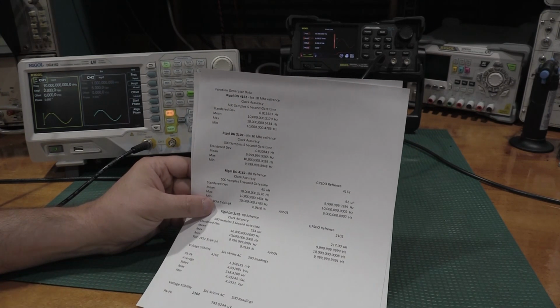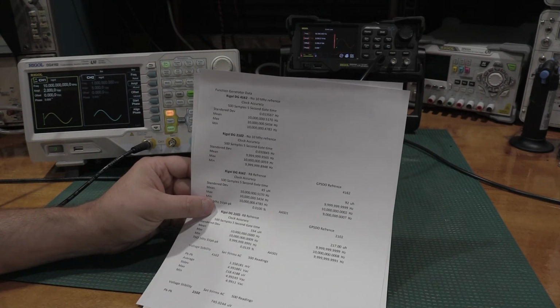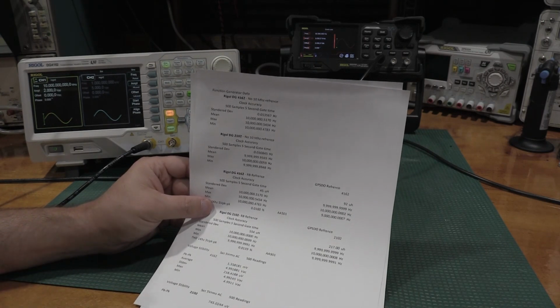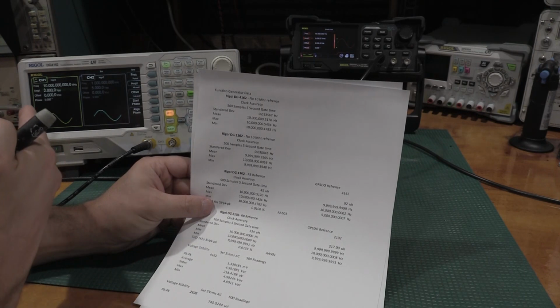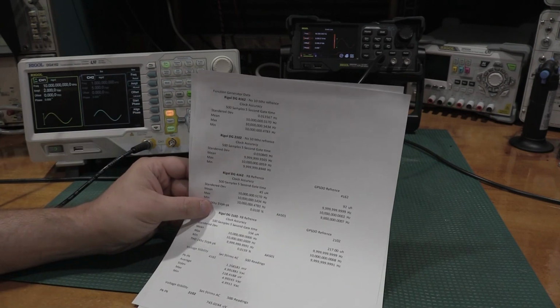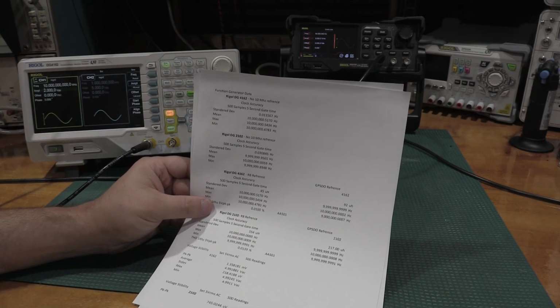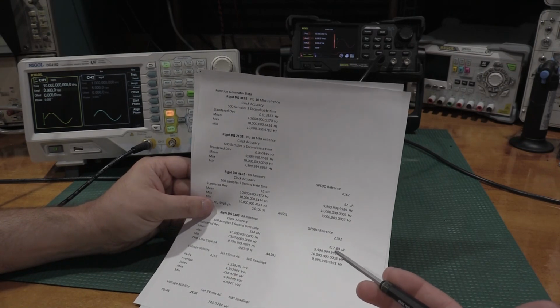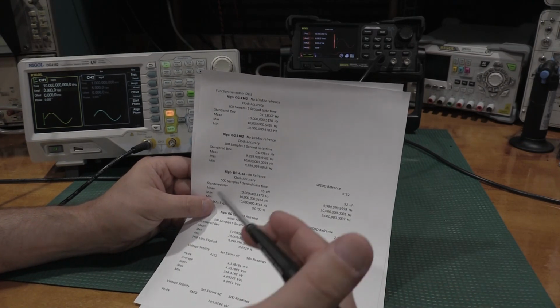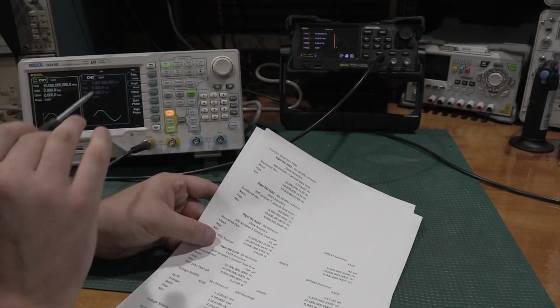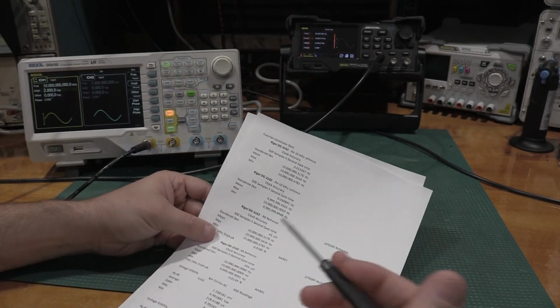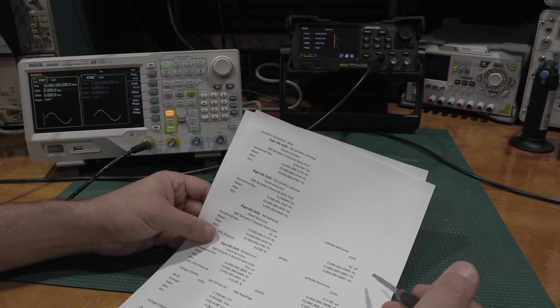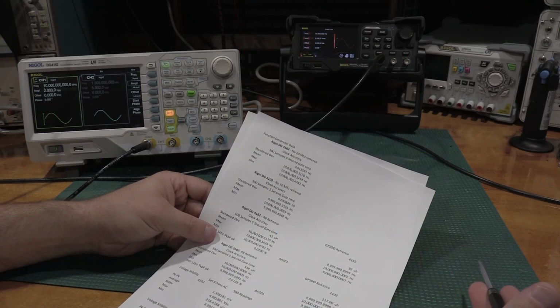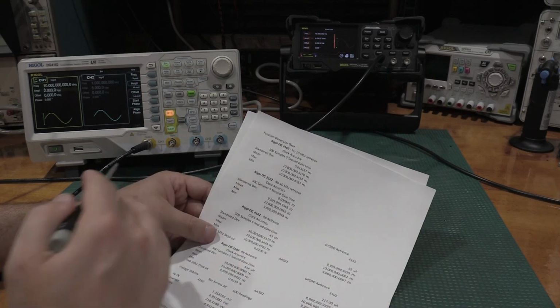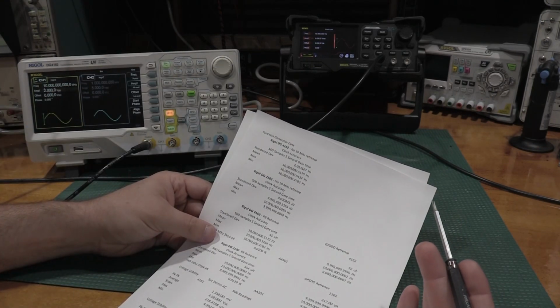Now, as I'm going through some of this, if you buy a 4162 from Rigol or a 2102, these specifications are not guaranteed. These are tested for these two units specifically. The spec sheet that you get from Rigol is the absolute worst case scenario. Anything better than that is a bonus, but that's what the units are guaranteed to do.